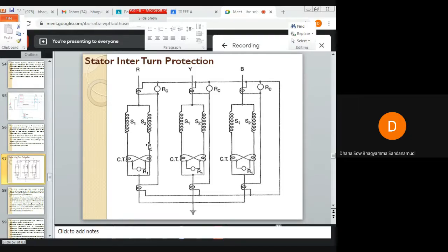But in practice, engineers think it is unnecessary to provide protection for interturn faults. Why? Because they invariably develop into earth faults. Even if an interturn fault occurs, it will develop into an earth fault. If an earth fault has occurred within a winding, then definitely we will go for merz-price protection. That's why engineers think there is no need to provide any protection for interturn faults.